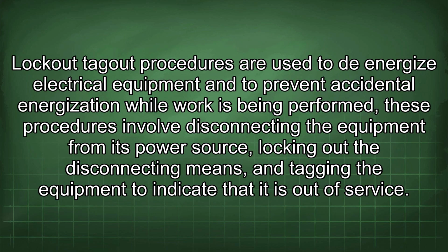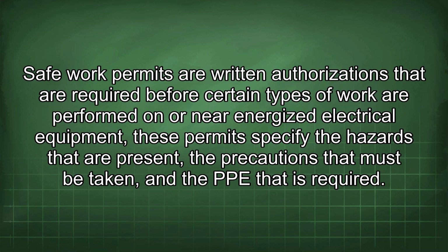Lockout-tagout procedures are used to de-energize electrical equipment and to prevent accidental energization while work is being performed. These procedures involve disconnecting the equipment from its power source, locking out the disconnecting means, and tagging the equipment to indicate that it is out of service. Safe work permits are written authorizations that are required before certain types of work are performed on or near energized electrical equipment. These permits specify the hazards that are present, the precautions that must be taken, and the PPE that is required.